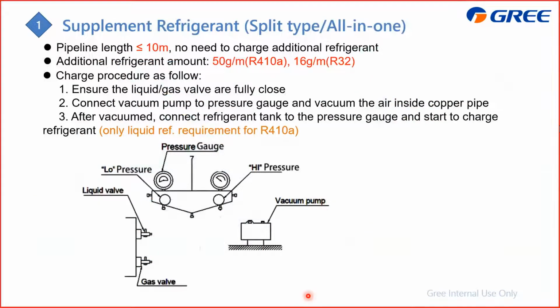And the last part is to charge the refrigerant, which is based on the on-site piping length. If the piping length from the outdoor unit to the indoor unit is less than 10 meters, there's no need to charge any refrigerant. If it's longer than that, for every extra meter, we require charging additional refrigerant.